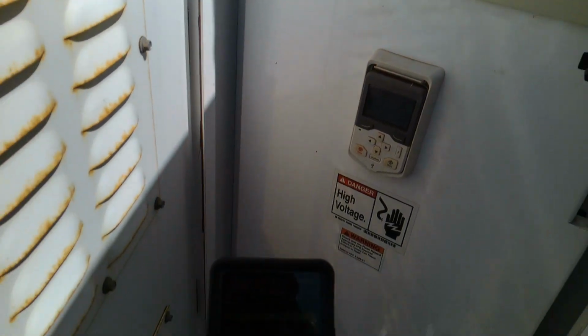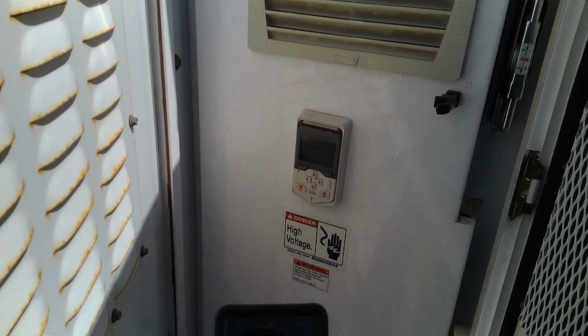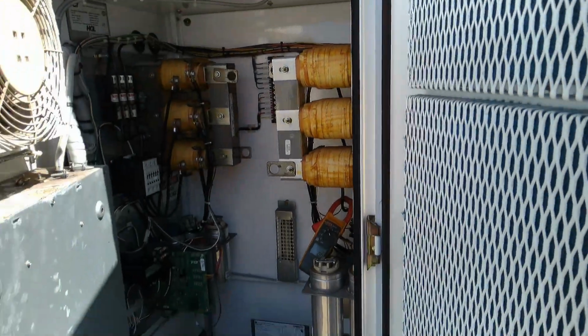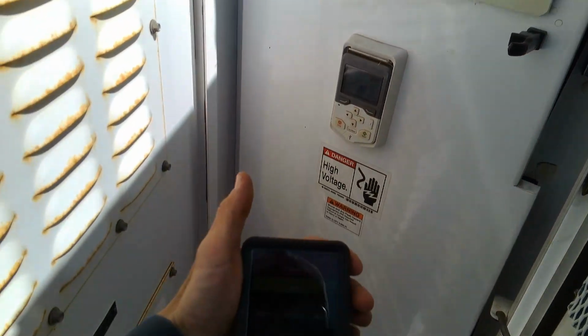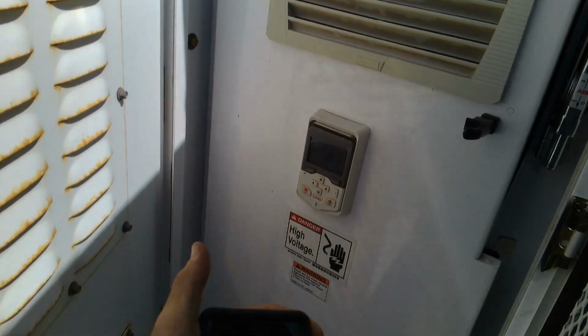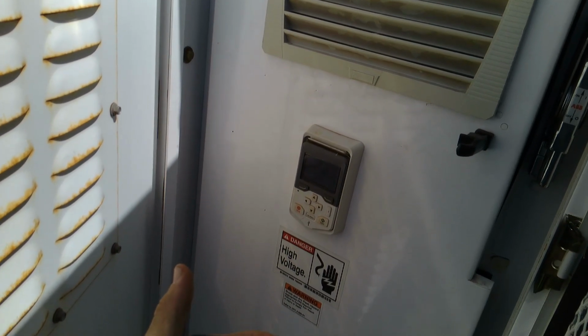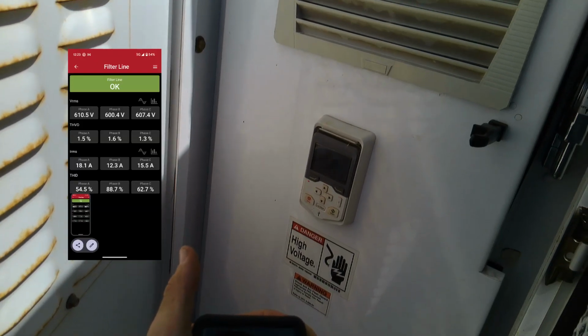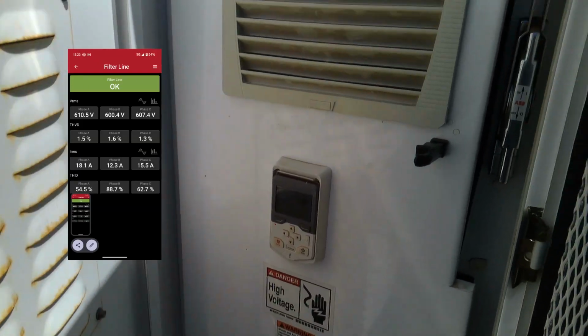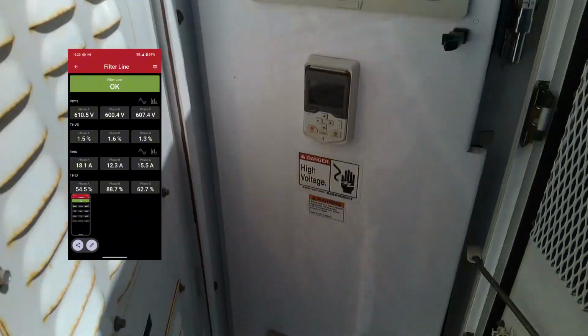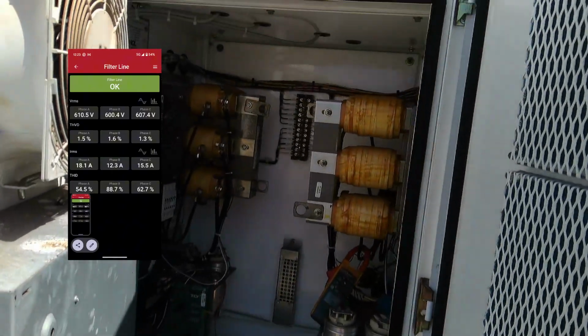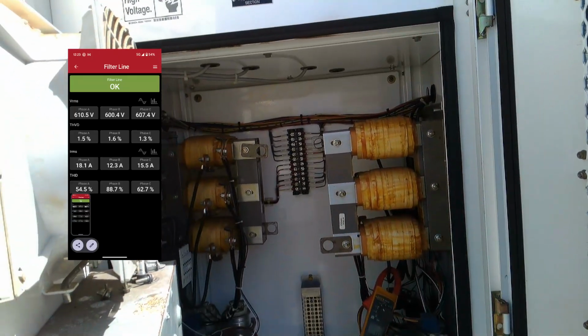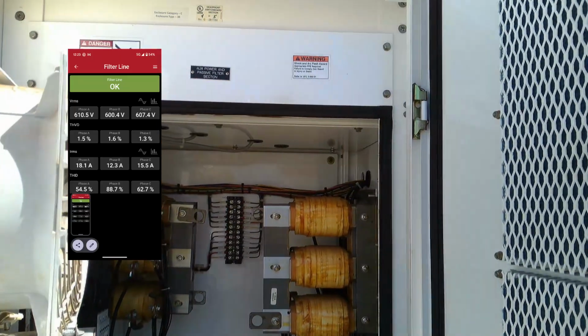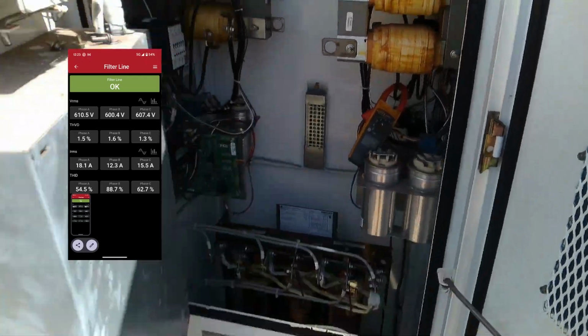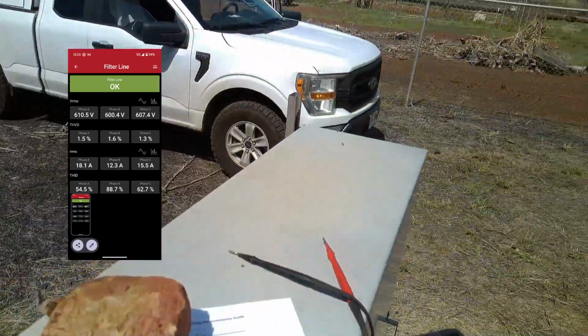There it is. Snap a shot. That was at 3 hertz, 4 hertz. Contactor's not even sucked in. 8, 10, 22 hertz, 31 hertz. 31 hertz it tripped. It tripped and the contactor didn't suck in at all during any of that.